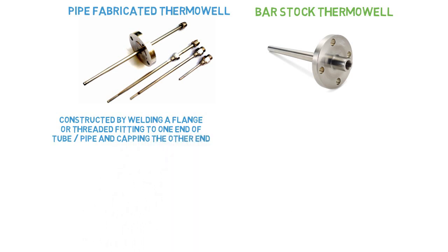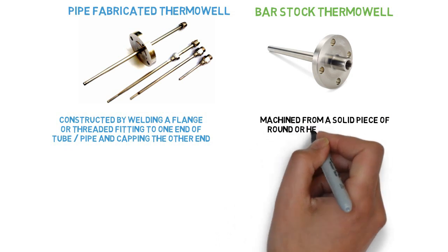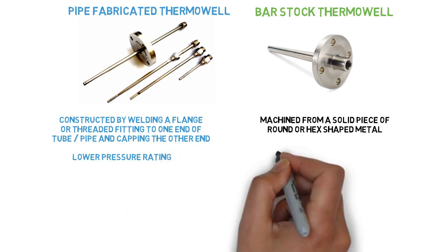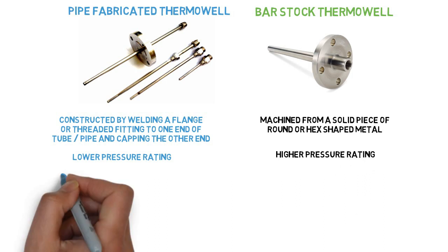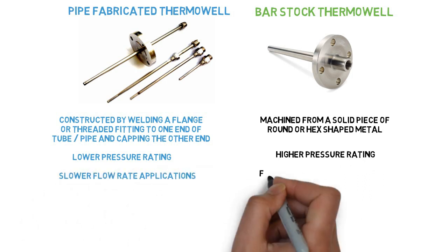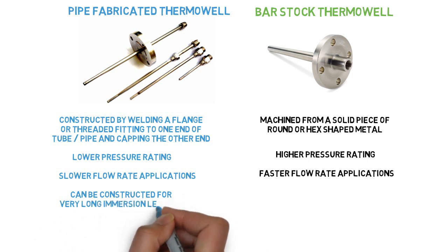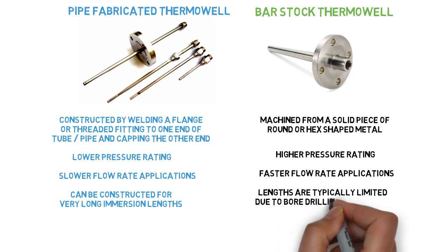A pipe fabricated thermowell is constructed by welding a flange or threaded fitting to one end of a tube or pipe and capping the other end. Bar stock thermowells are machined from a solid piece of round or hex-shaped metal. Pipe fabricated thermowells have a much lower pressure rating, while bar stock thermowells can withstand higher pressures. Pipe fabricated types are used for measurements where flow forces are low; bar stock types are suitable for faster flow rates. Pipe fabricated thermowells can be constructed for very long immersion lengths, while bar stock lengths are typically limited due to bore drilling limitations.